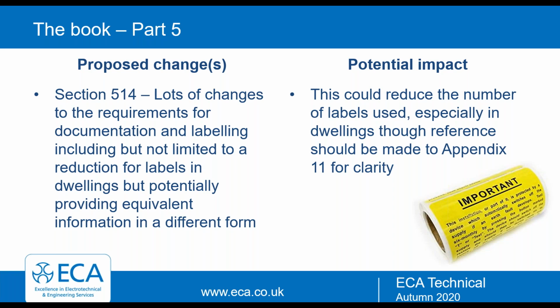Oh, we do like a sticky label, don't we, labels, in our industry we do that. Lots of changes in section 5.1.4, one of the areas being a potential reduction for labels on dwellings. Good thing, bad thing? Depends who you ask. What they're saying is for domestic premises, for dwellings, you don't need the various labels stuck on the front of the consumer unit: the periodic inspection notice, the RCD test button notice, and the mixed colours label. If there are old and new wiring colours within a board, those three labels don't need to be there if it's a dwelling we're working in.